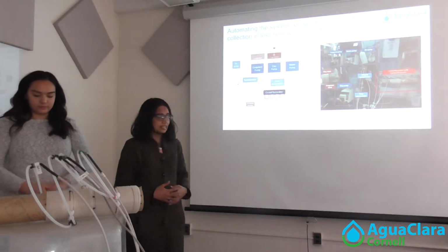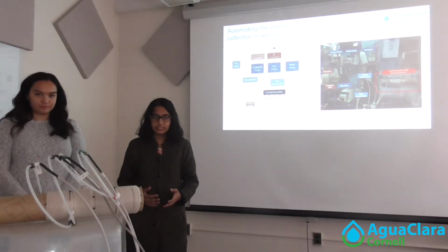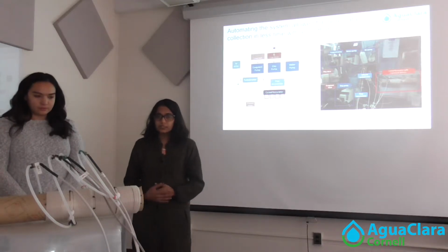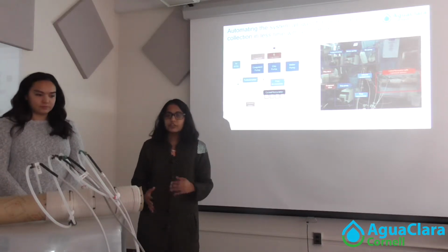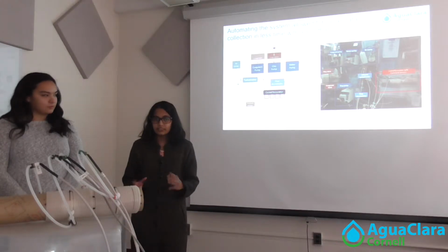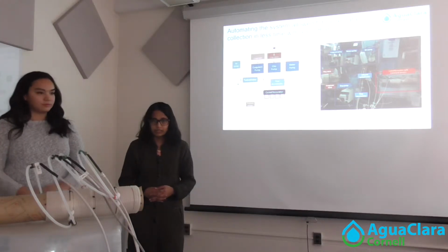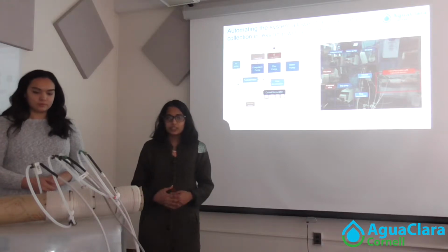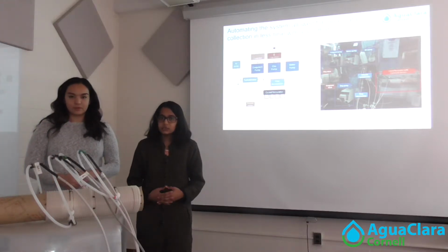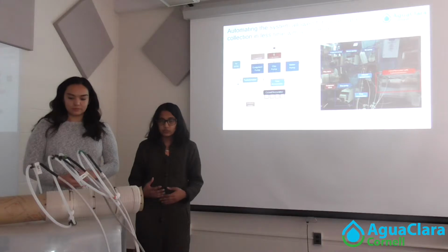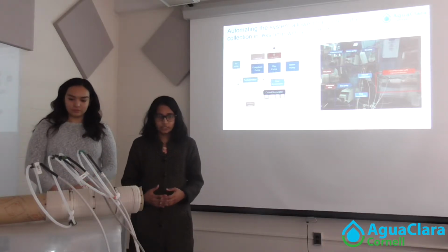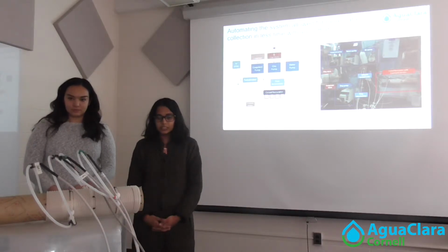This slide shows the experimental setup CNARC used this semester. Water flows in through the influent pipe and is pumped into the flow accumulator. The flow accumulator dampens any fluctuations in the water caused by the pump. The water flows out of the flow accumulator, after which clay is pumped in. The rate at which clay is pumped in is controlled by the PID controller, and this is determined by the target turbidity. And the turbidity is measured by the turbidimeter.